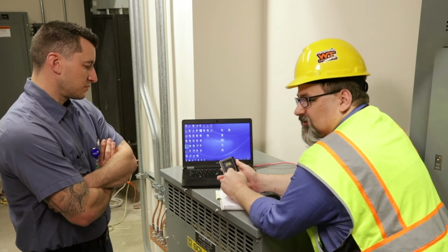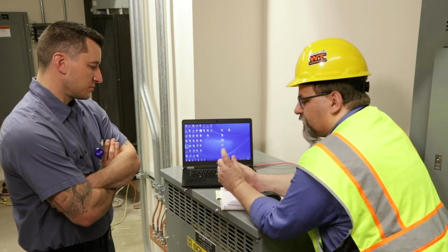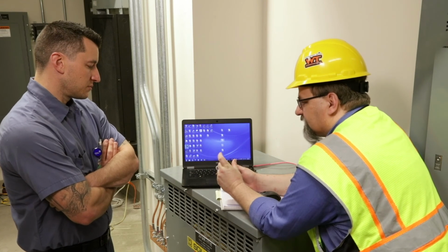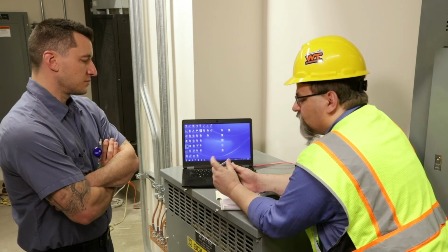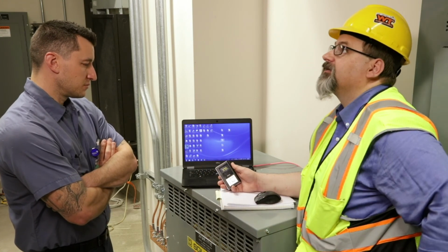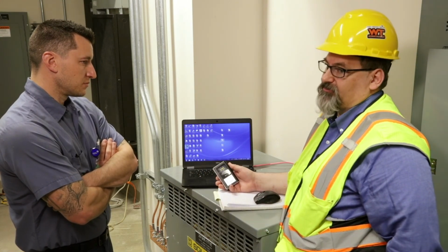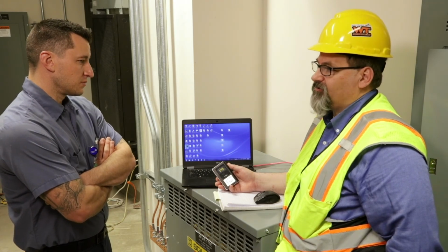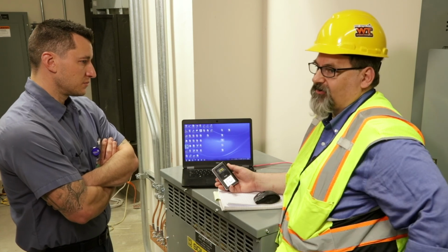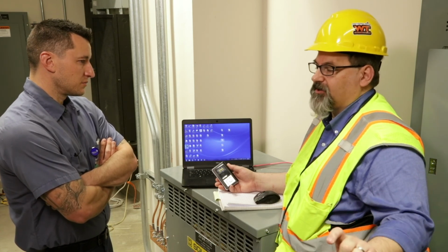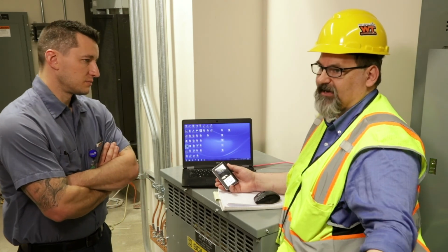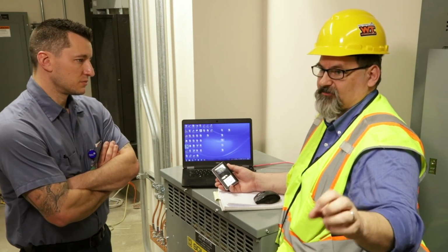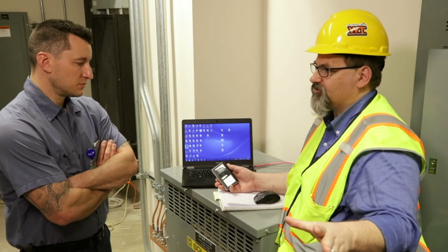Once you have that information, then you just set this into test mode. That sensor goes to a mode where instead of taking 20 minutes to trigger, it takes 10 seconds, essentially. So you put it in test mode, you stand still underneath the sensor and you watch the blue and red lights. The blue and red lights aren't going off. You count to 8 and the sensor should trigger off. That whole room will go off at that time and the plug loads will turn off, right? And then you wave your hand again and the plug loads will turn right back on. So you'll be able to test the plug loads real easily to make sure that they're working.